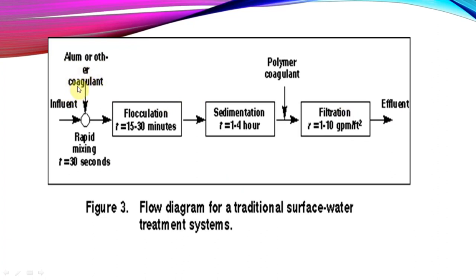This is much more complicated than slow sand, where there was no coagulant - only gravity action. Here, coagulant is added as the first part of purification, coagulating all particles into flocs. After flocculation, slow stirring of the water by paddles forces floc formation, and the flocs settle. Since this is done at a rapid pace, there is no long waiting time - in slow sand there is a 3 to 12 hour wait, here it is only 15 to 30 minutes for flocculation and then sedimentation. Then the water is sent for filtration.